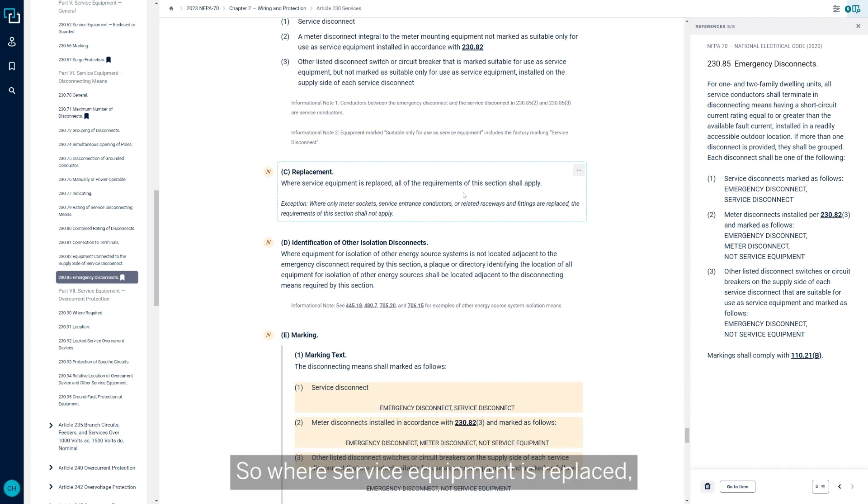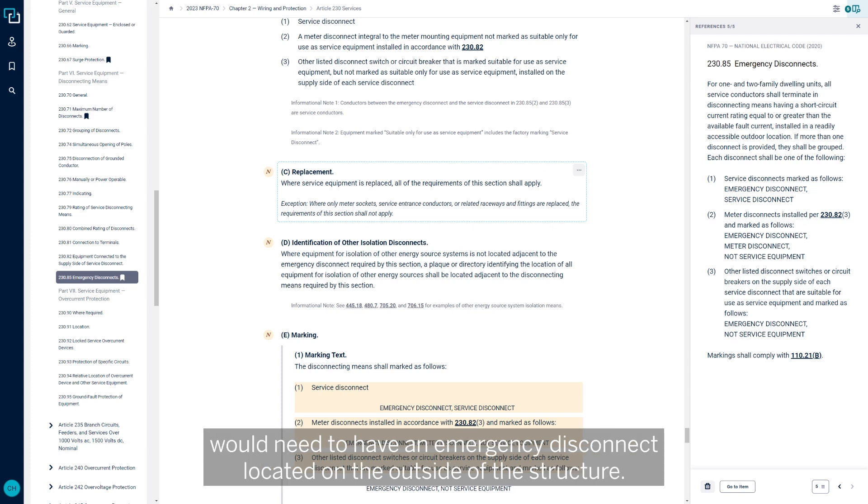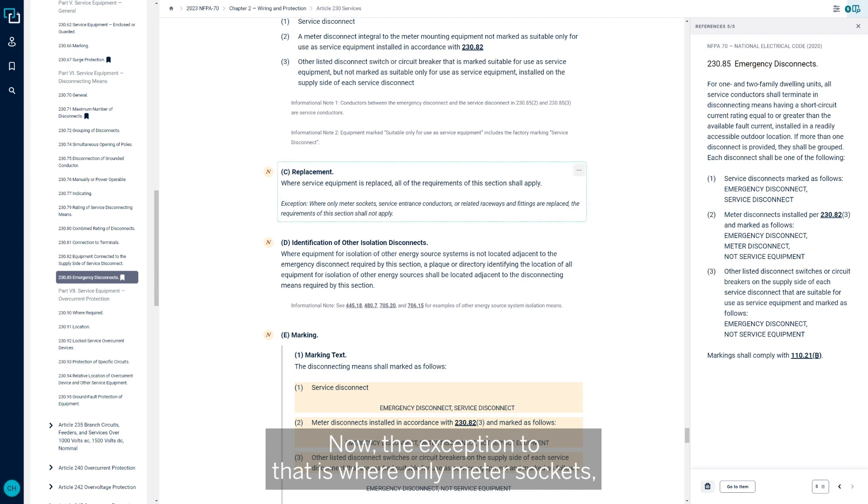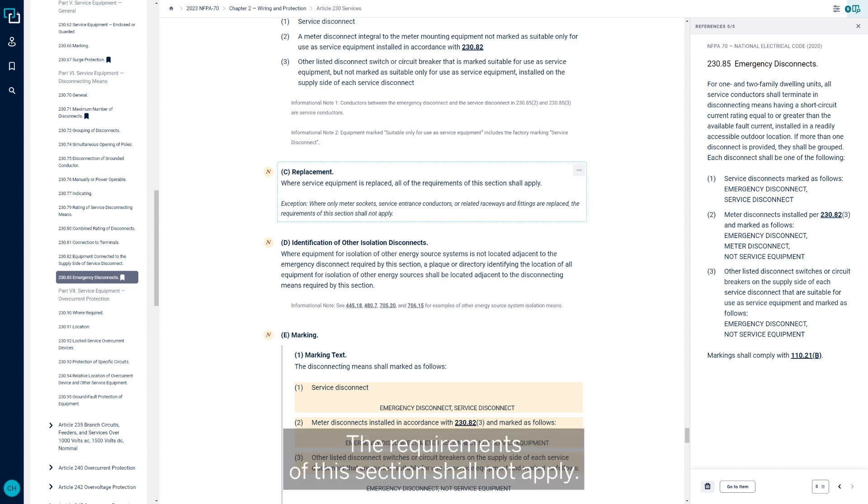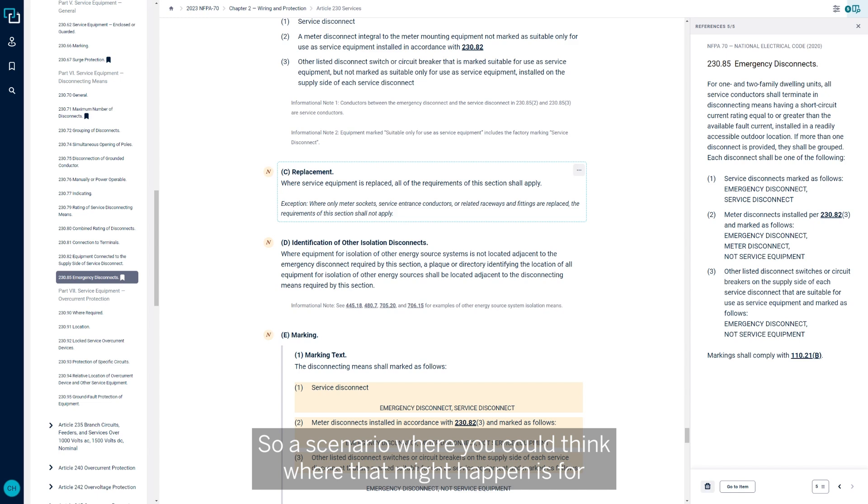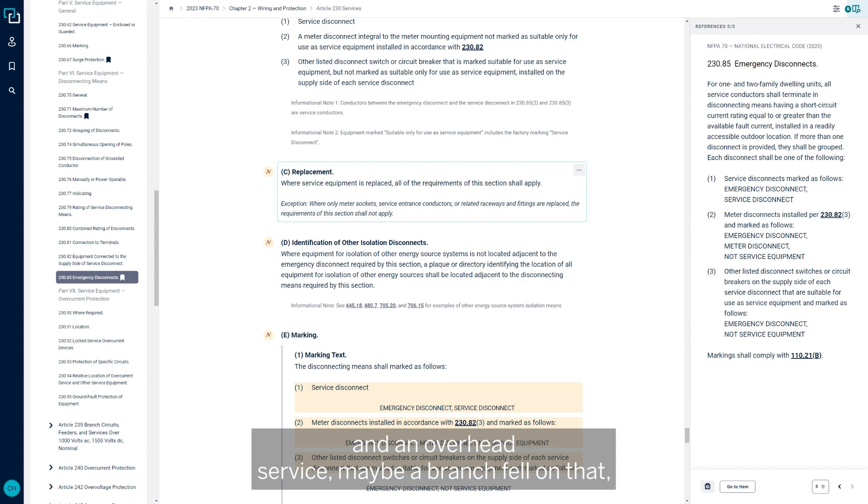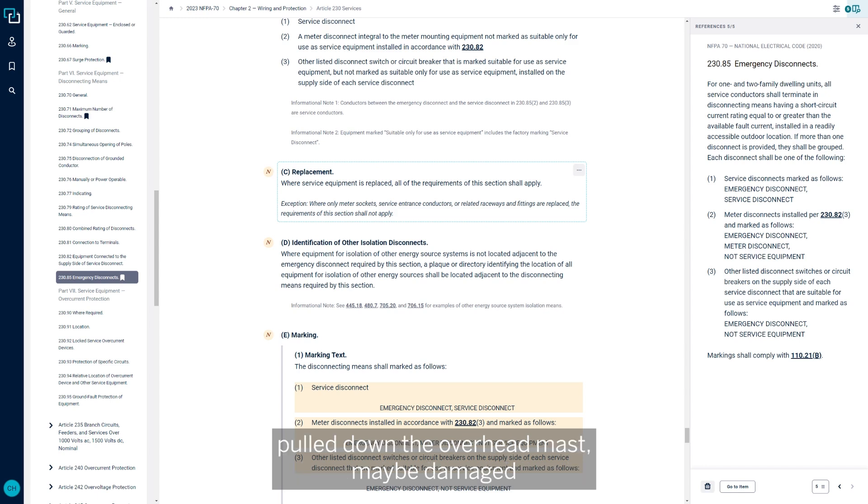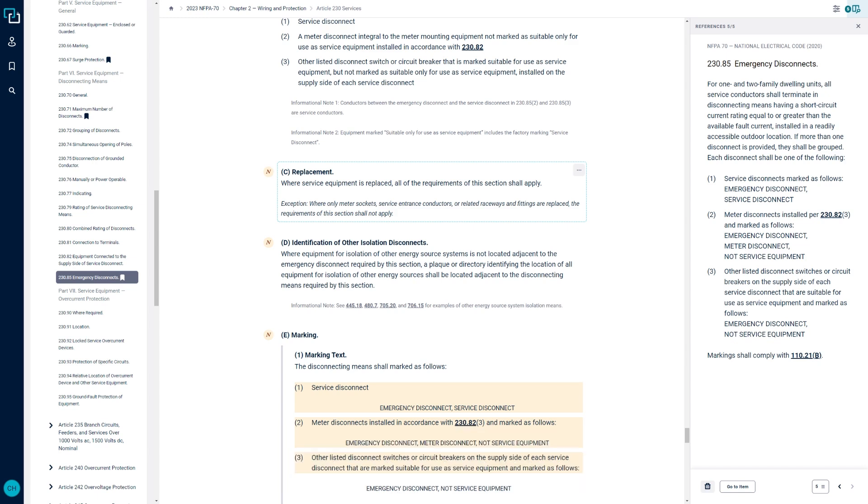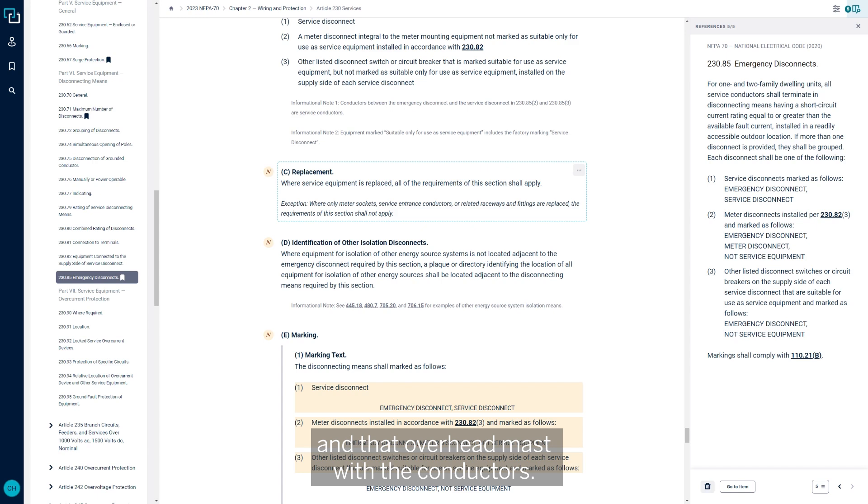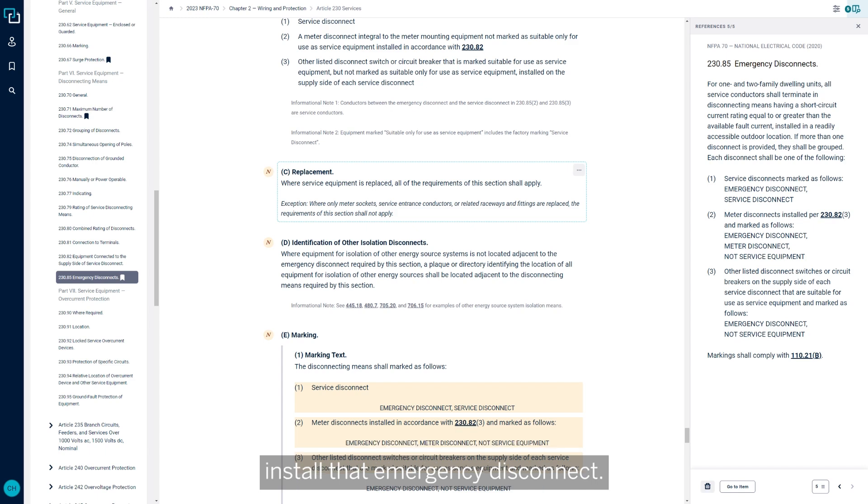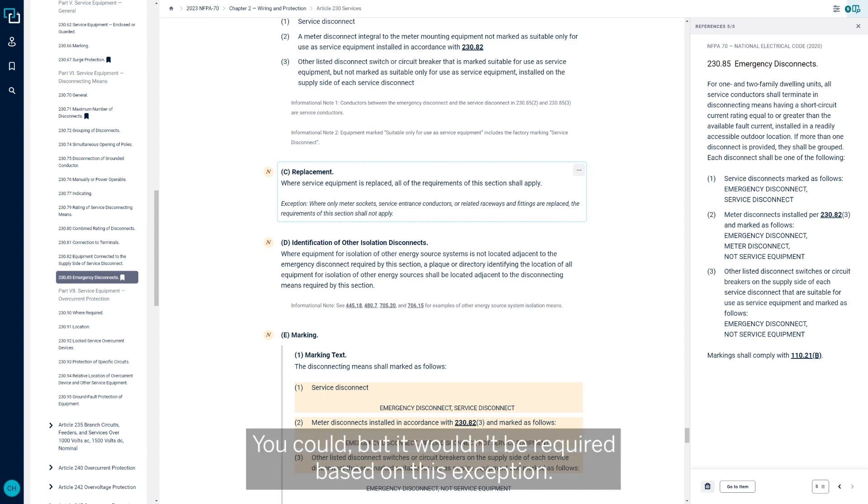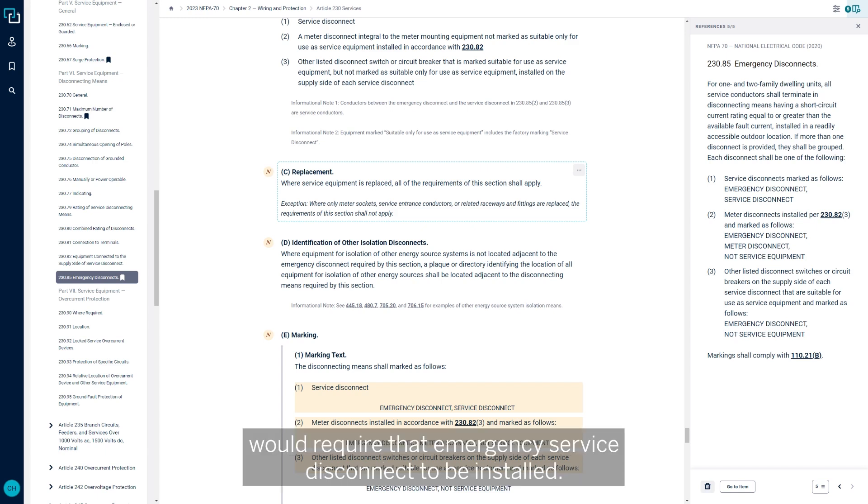Options are given for what the disconnects can be. You have a service disconnect, a meter disconnect that's integral to meter mounting equipment, and then another disconnect or switch circuit breaker that's marked for suitable service equipment. Replacement is a key piece that was added in the 2023 NEC. Where service equipment is replaced, all of these requirements shall apply. So in the case where a service is being upgraded, that new service would need to have an emergency disconnect located on the outside of the structure. Now the exception to that is where only meter sockets, service entrance conductors, or related raceways and fittings are replaced, the requirements of this section shall not apply. A scenario where that might happen is there was an ice storm and an overhead service, maybe a branch fell on that, pulled down the overhead mast, maybe damaged the hub in the meter to the point where you have to replace the electrical meter. So now you're just replacing the meter itself and that overhead mast with the conductors. In that particular case, there's an exception there that you would not have to necessarily install that emergency disconnect. But any new services or service upgrades would require that emergency service disconnect to be installed.